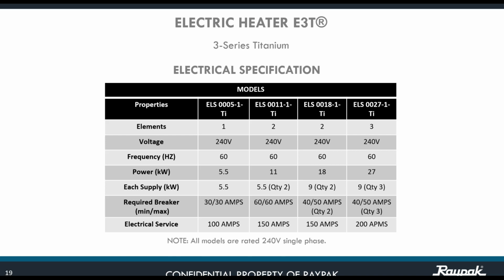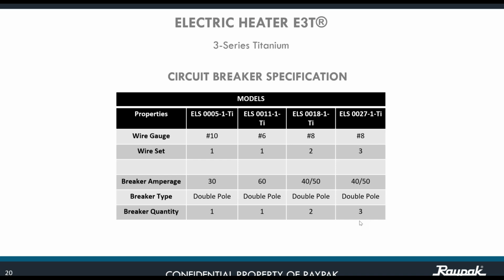Think about the electrical service panel. What size do you have to have? You see it here at the bottom. You need to have 100 amps for the 5.5, 150 amps for the 11 kilowatts. For the 18 kilowatts, you need to have 150 amps. And for the 27, you need to have 200 amps. Okay?